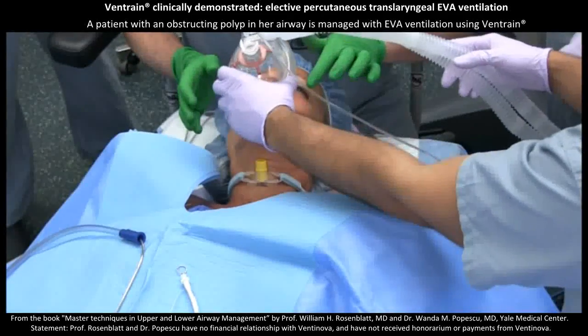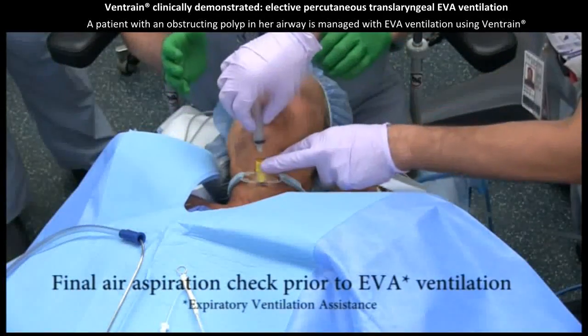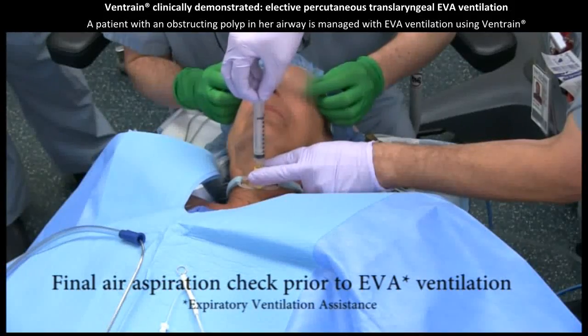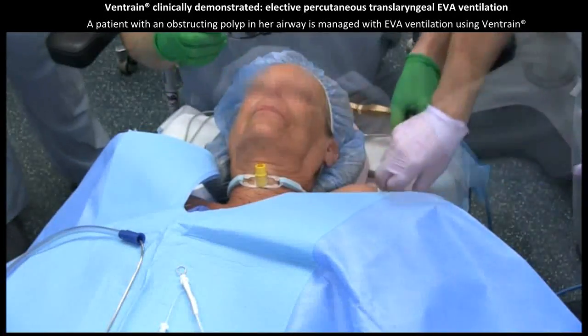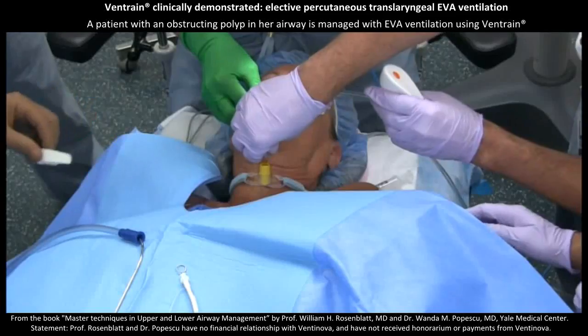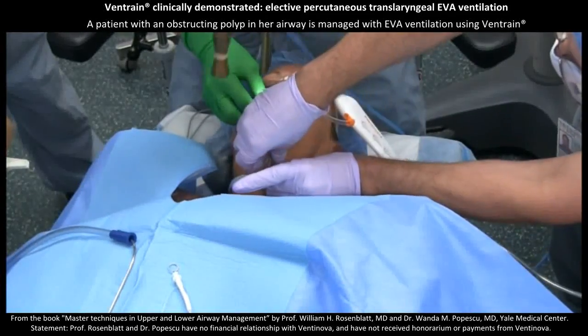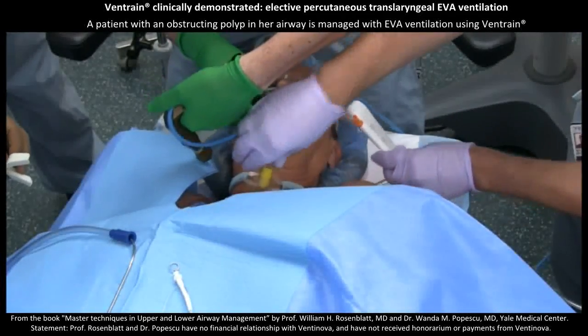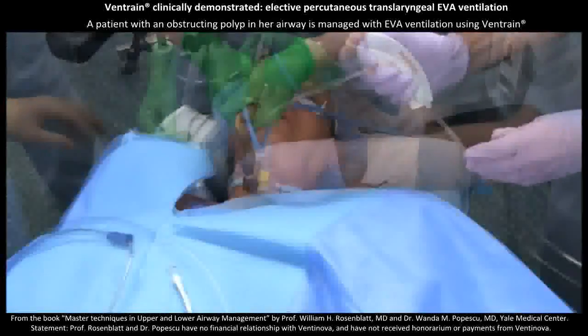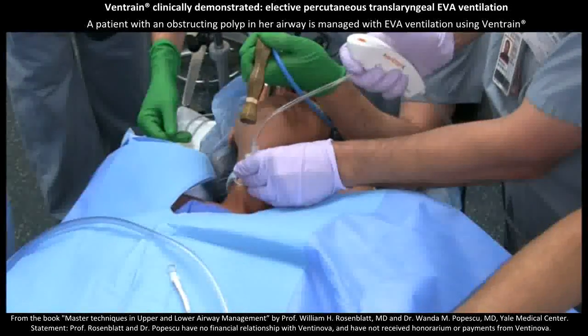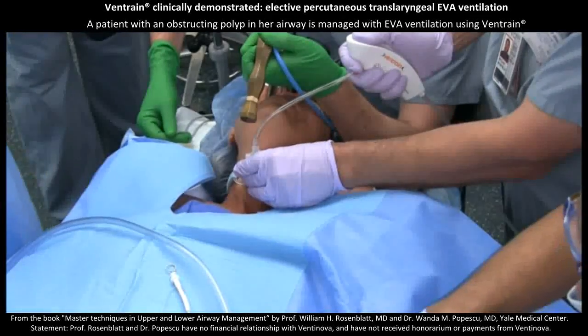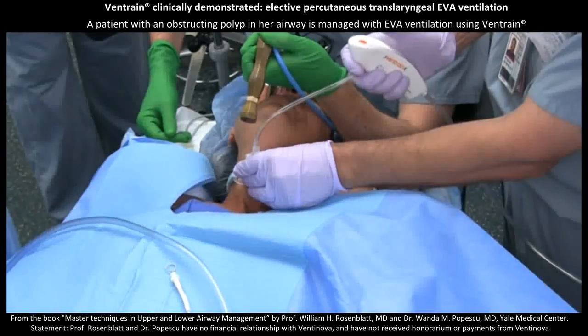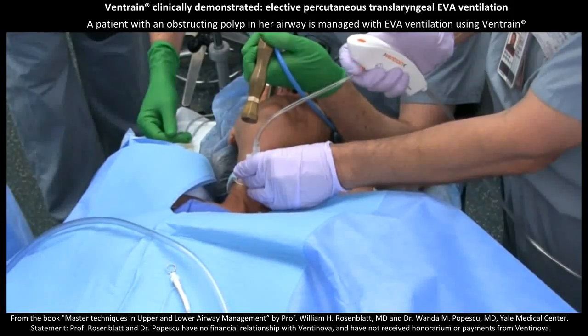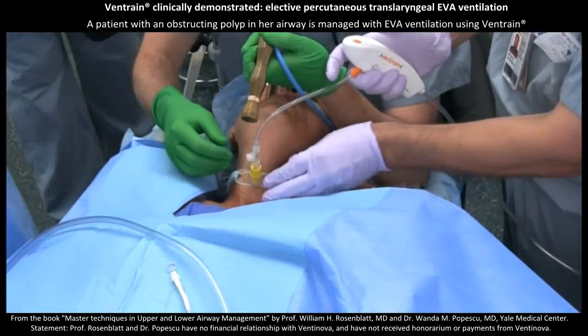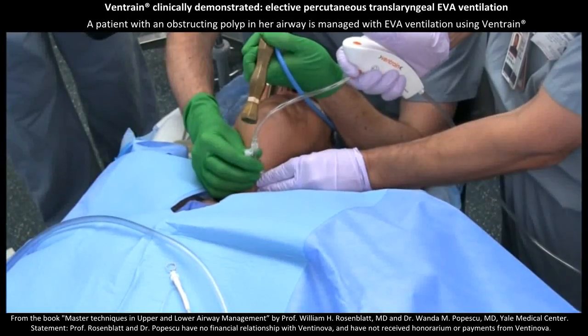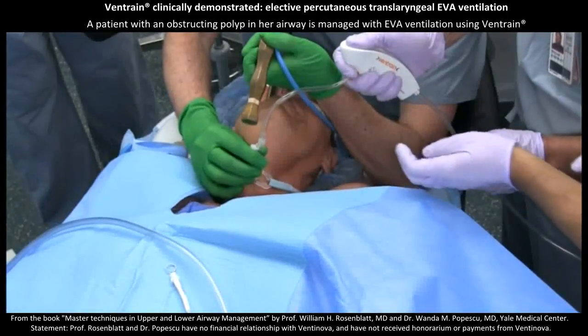Following pre-oxygenation, the patient underwent an IV induction of anesthesia and maintenance with TIVA. A single-use Ventrain EVA ventilation device was attached to the trans-cricothyroid membrane catheter. Using a pressure-compensated flow meter set at 15 liters per minute, the patient was ventilated with an I/E ratio of 1:1 with approximately 1 second inspiratory and expiratory times. After each 5 cycles of inspiration and expiration, an equilibration pause was taken.